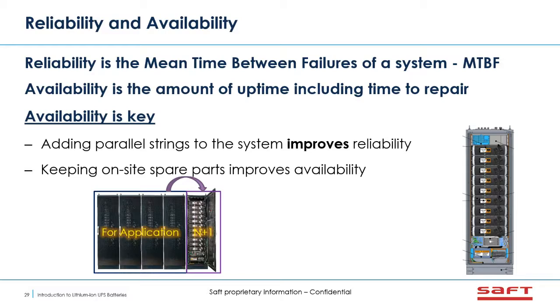The other thing now with lithium-ion batteries is what we do is if you have that same design for cabinet requirement for your application, we can actually remove a cabinet, run the simulations, and see what type of runtime you get out of it. So typically, generators can start in 10, 15 seconds, and they're online within 30 seconds. We can see how much runtime you get for that critical changeover of power from the loss of utility feed to your generators to make sure that battery system is well equipped, even if you lose a cabinet.